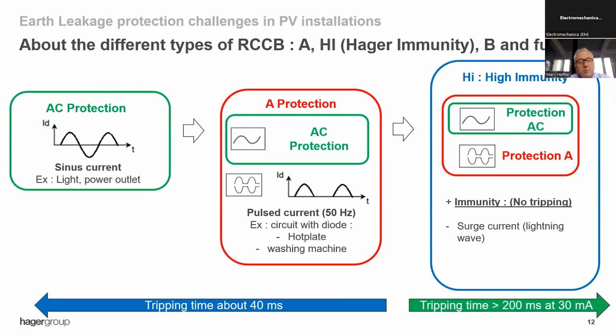So here we go through the different types of RCCBs existing in the market. You have the classical old AC type, which is no more used. What we sell, for example, is only A type. The A type is able to do what the AC is doing, but it is also able to detect pulse current leakage. For these devices, the tripping time is about 40 milliseconds because there is no electronic assistance.